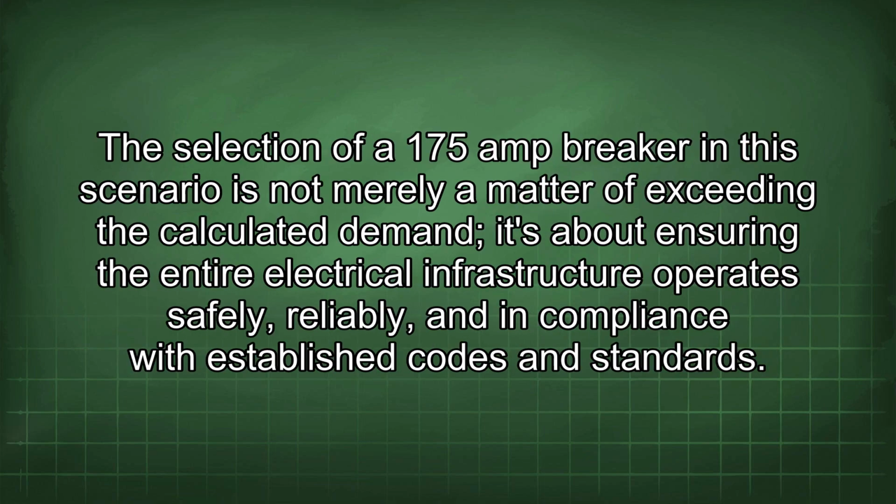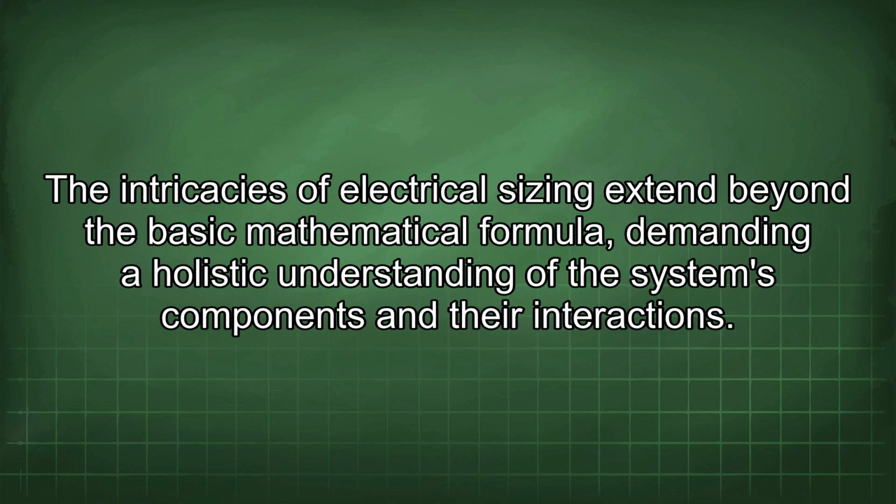The selection of a 175 amp breaker in this scenario is not merely a matter of exceeding the calculated demand, it's about ensuring the entire electrical infrastructure operates safely, reliably, and in compliance with established codes and standards. The intricacies of electrical sizing extend beyond the basic mathematical formula, demanding a holistic understanding of the system's components and their interactions.